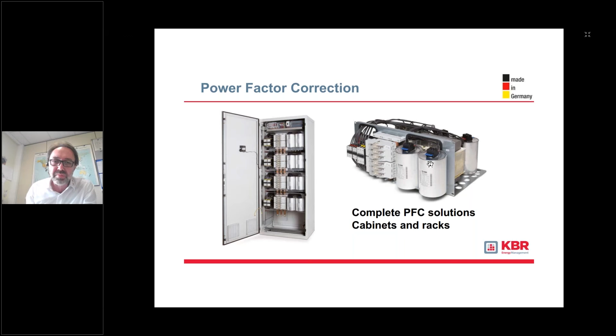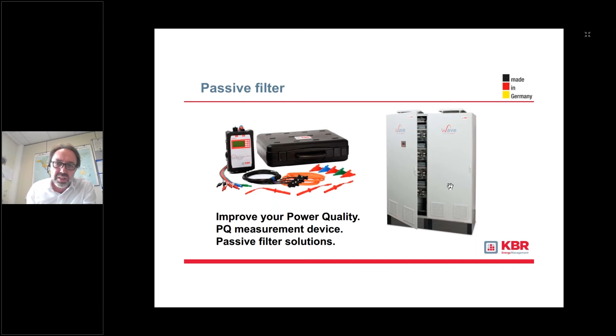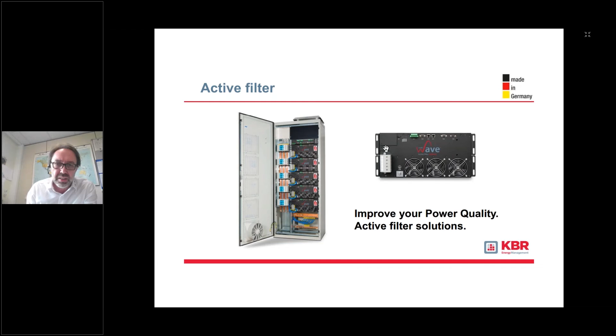For dimensioning of a power factor correction unit, it's necessary to have equipment for power quality analysis. For that, we use our multi-log device, which is a mobile PQ analyzer, a class A device. And in that way, we can also dimension filters. So here we see a passive filter, which we produce at KBR. But we also have active filters in our product range to improve the power quality at the customer site.